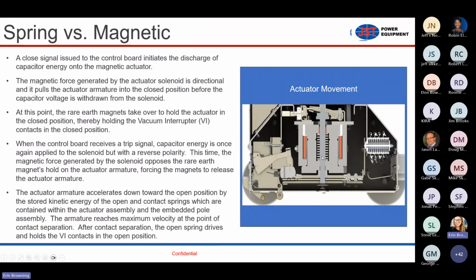No, that's not gonna introduce sag, and it's not gonna lose force similar to the large springs that you see in a traditional breaker. This is an open assist. Most of the time the breaker is closed, because there's current flowing through the vacuum bottles. The system's energized, the breaker's closed, so that spring is compressed most of the time. When we see it operate is when the armature moves down and that spring decompresses, which is its natural response, and it flings the armature downward. That's happening so fast. It's faster than a 3-cycle time frame that the breaker's rated for. In 10,000 operations, we didn't see any significant decrease in breaker opening time.